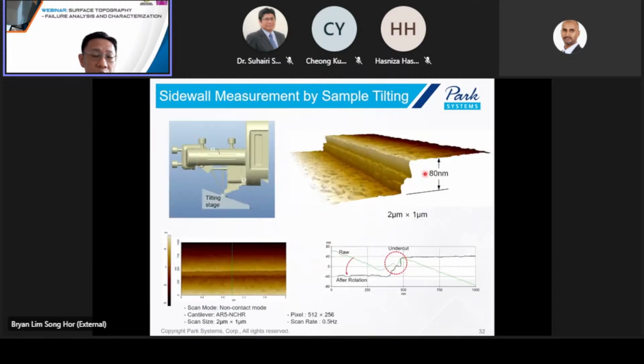Okay, so AFM can also measure sidewall roughness. So this is a sample. There's some undercut, and sometimes we need the roughness information of the sidewall. So with a tilting stage, the AFM can measure the sidewall roughness by tilting the sample sideways. Once we get the scan, we can use software to rotate it back and find the sidewall roughness or line edge roughness, line width roughness, etc.